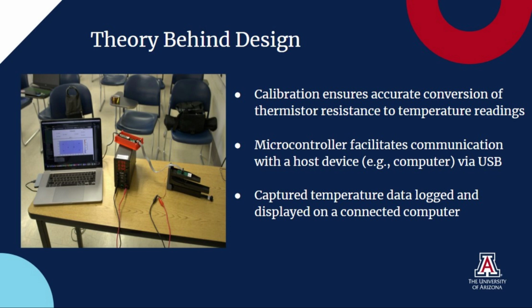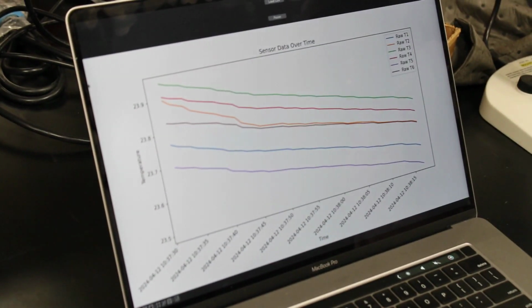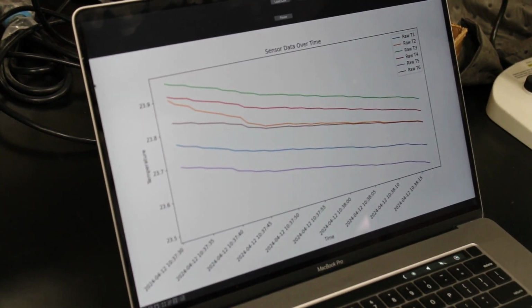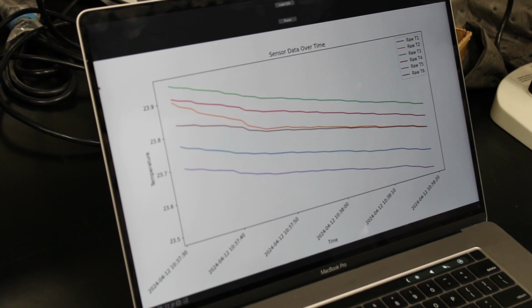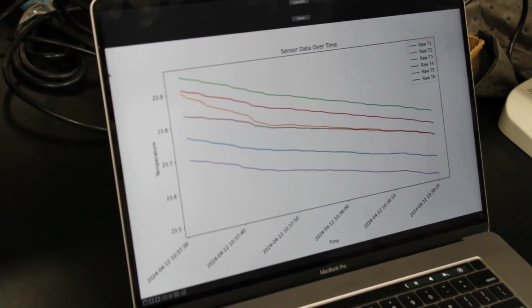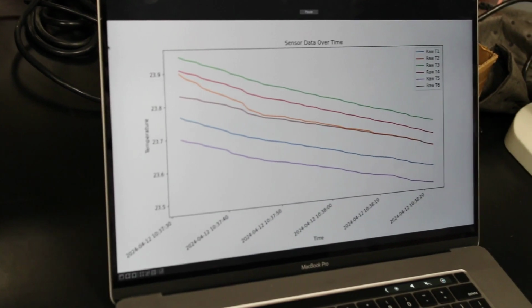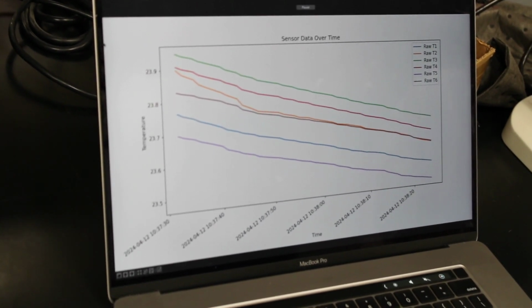A heat transfer model of the sensor assembly was developed using ANSYS Discovery to simulate the temperature distribution across the glass slide and determine the delta T between the slide and various thermistor assembly configurations. The objective of the model was to optimize heat transfer within the system and provide accurate temperature readings at our desired accuracy range of 40 to 100 degrees Celsius.